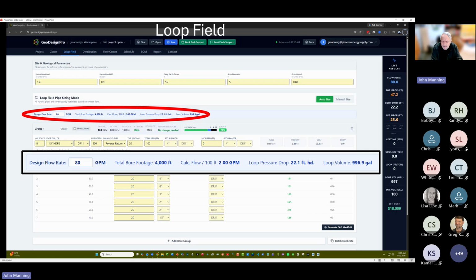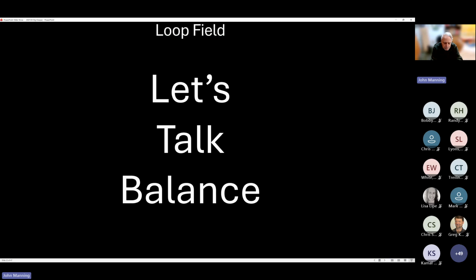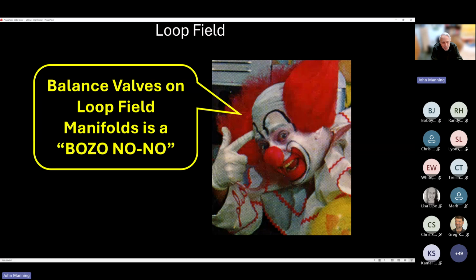If you go below 1.5, and especially significantly below 1.5, I would suggest your loop field is over-designed. If you go way above 2.5, up to 3 GPM, I might question that loop field is undersized. So these are just key parameters to help guide a design. But I want to take a minute and talk about balance. It's sort of a pet peeve of mine that I feel strongly about balance valves on loop field manifolds. And if there's any doubt about how I feel about those things, hopefully this removes any doubt. I've been to too many jobs where balance valves were installed on the manifold, and they're all in a wide open position. Nobody uses them to balance loop field flow.